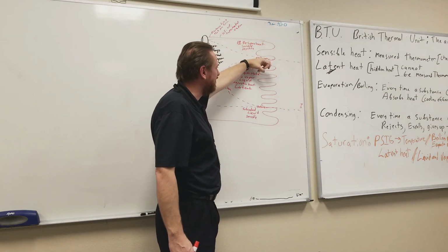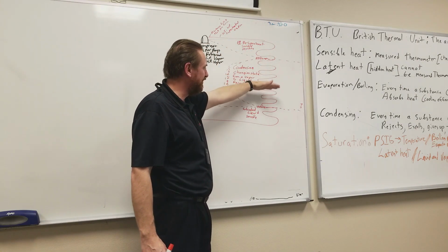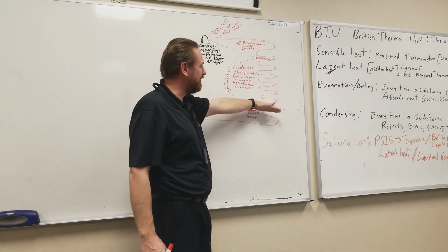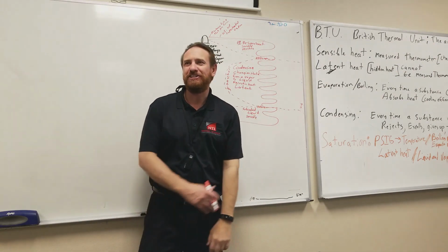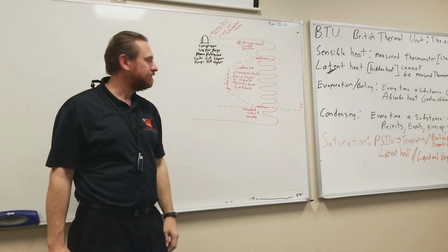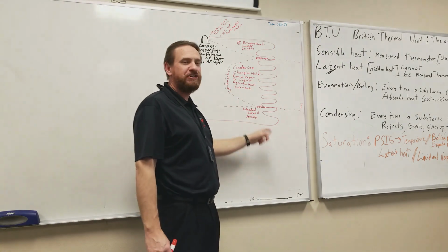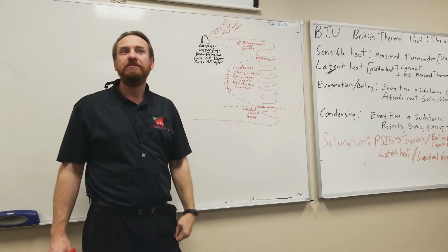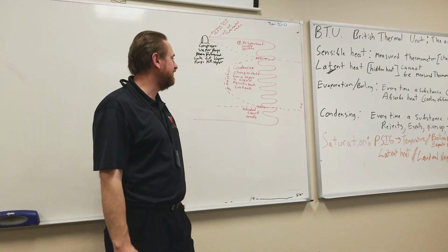Now it starts to rain liquid refrigerant. Now that's all liquid, and I can drop the temperature of that liquid below saturation. So all of this has to be warmer than the air temperature. As subcooling, are we still rejecting heat? Yes, still rejecting heat.